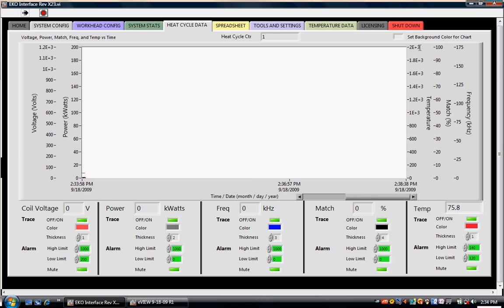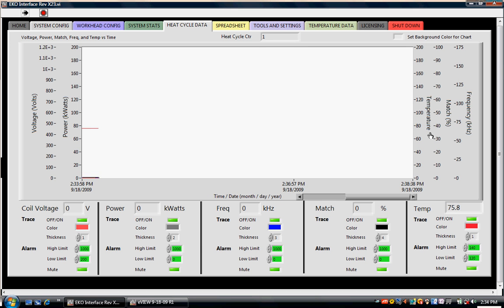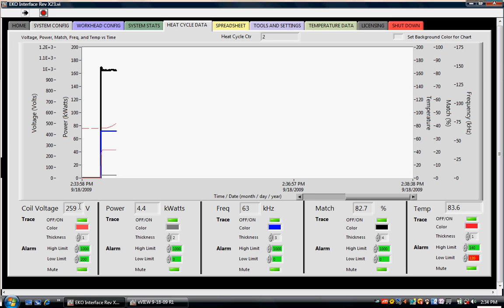We are going to rescale the temperature so that it reads from zero to 200 degrees F. I'm going to go ahead and start a heat cycle from the front panel of the EKOHEAT. Now we can see right below the graph we've got digital displays that indicate coil voltage, power, frequency, percent match, and temperature for each one of these traces on the graph. We can turn the trace on and off. Right now coil voltage is 259 volts.